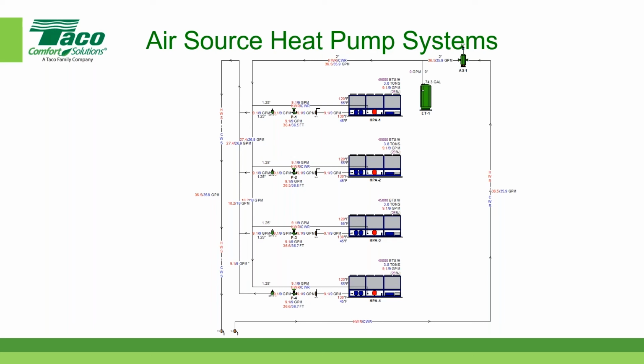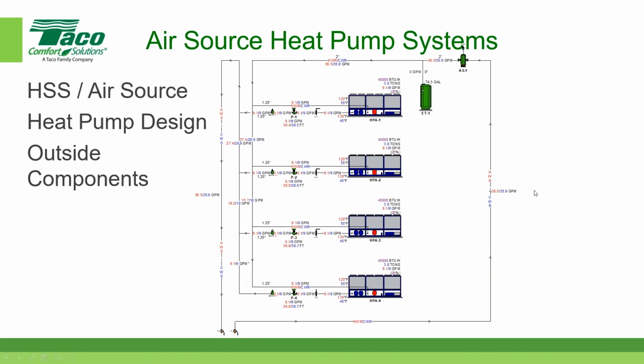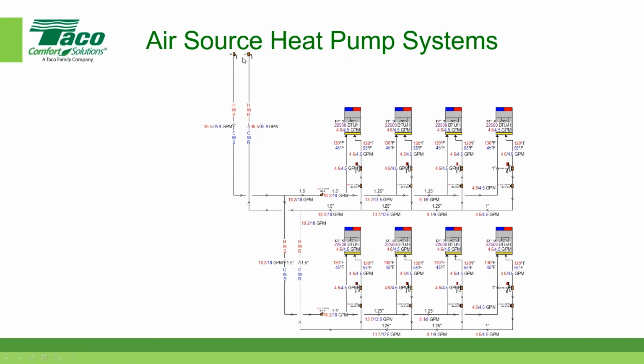I picked 4 air to water heat pumps. You can see the temperatures. I don't know if you can read them, Brett. They're kind of small, but there's 130 leaving, 120 returning for the heating. When it's in the cooling mode, we have 45 leaving and 55 returning, 10-degree delta T on both sides. And if you go to the main circulating pump, I divided this, by the way, these pipe valves at the bottom left-hand corner, they continue onto the next screen. And so we have all of this wonderful stuff. And there are those valves again.